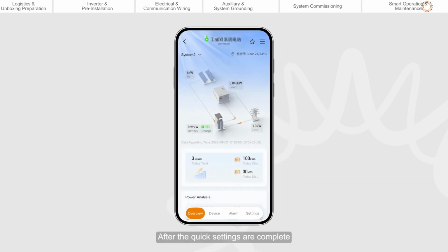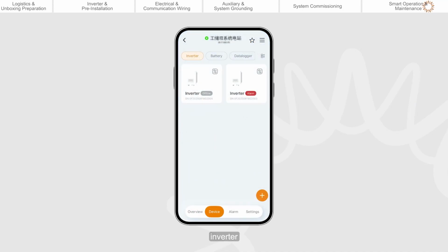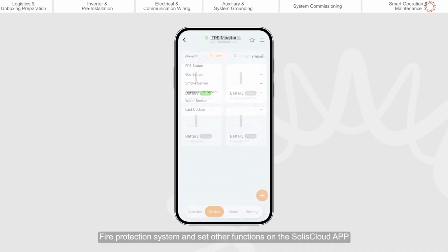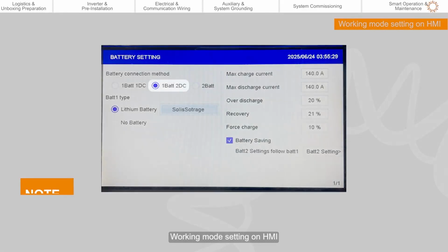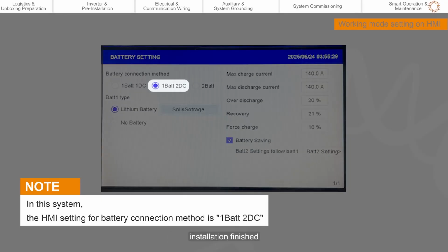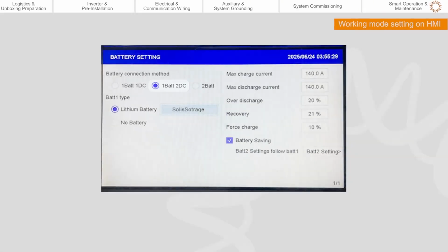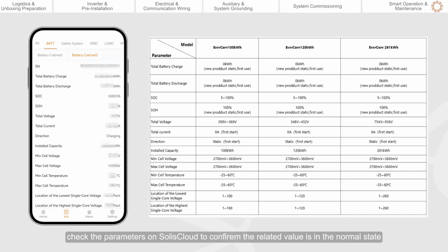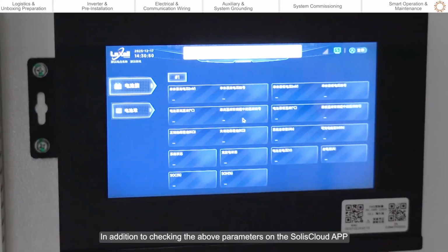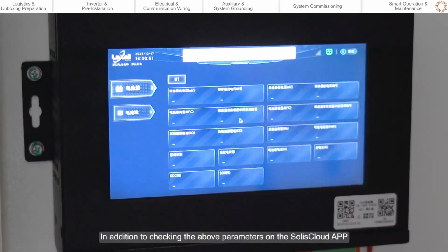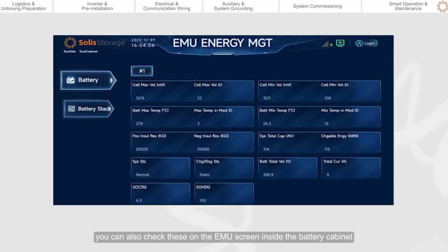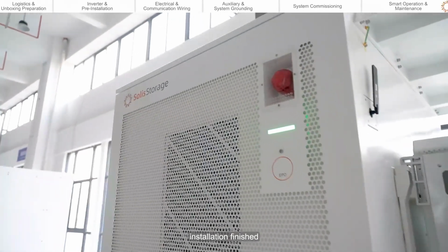After the quick settings are complete, you can see the plant information, inverter, battery, fire protection system, and set other functions on the SolisCloud app. Working mode setting on HMI. Installation finished. Check the parameters on SolisCloud to confirm the related value is in the normal state. In addition to checking the above parameters on the SolisCloud app, you can also check these on the EMU screen inside the battery cabinet or remotely log in the SolisCloud platform on a computer to check. Installation finished.